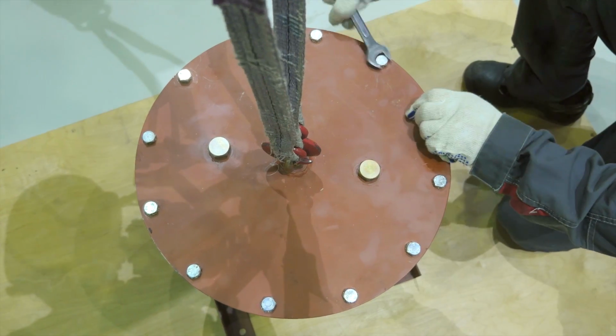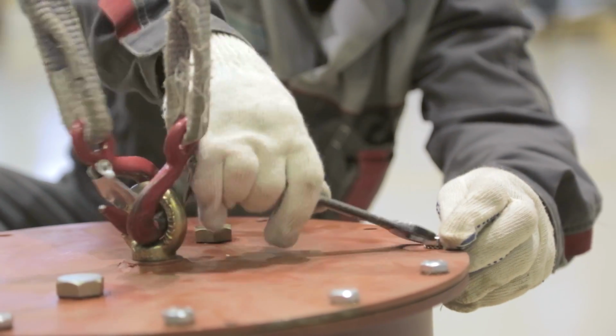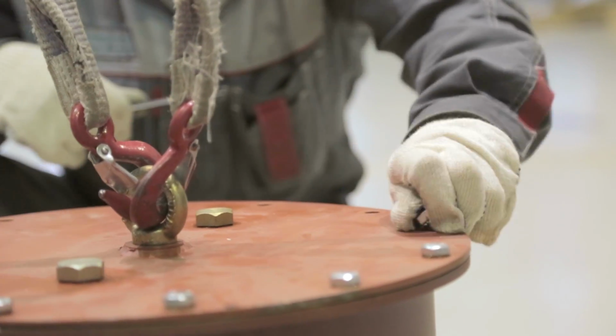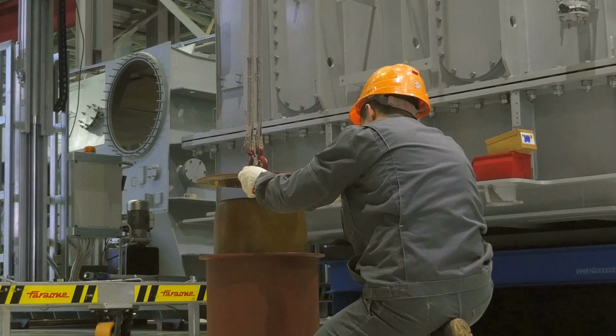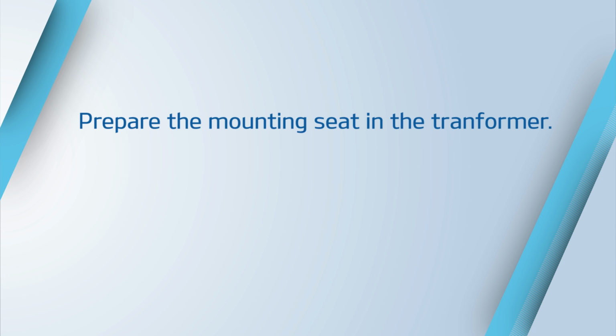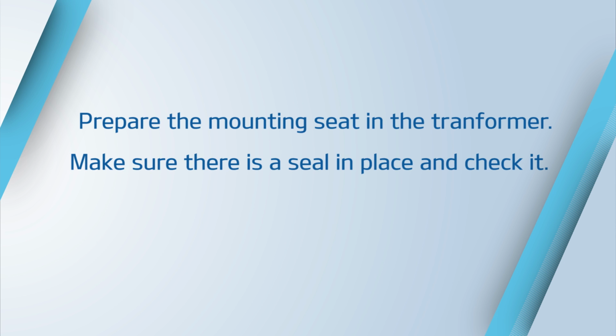Set the lower shield onto the transformer tap. If the shield comes with paper insulation, it is supplied inside a special oil tank. In that case, undo the tank lead bolting and accurately remove the shield, which is attached to the lead. Next, take off the shield from the lead and insert it in the transformer, passing flexible tap wires through the central hole. Thus we have prepared for installation. So let us repeat the most important steps. Prepare the mounting seat in the transformer, make sure there is a seal in place and check it.